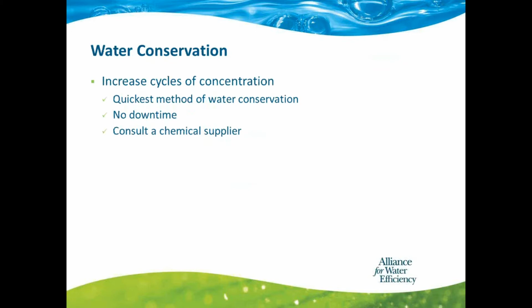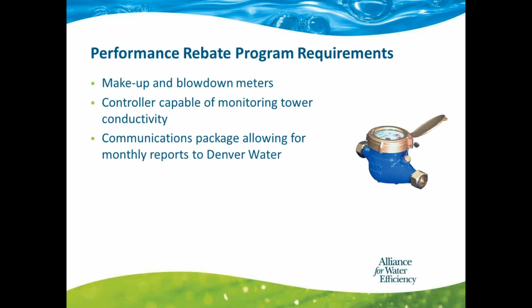The easiest way to save water in cooling towers, of course, is to increase the cycles of concentration. This is the quickest method we've seen for water conservation. There's no downtime, but you want to be sure to consult your chemical supplier, making sure that whatever path you choose does not harm the tower or the environment. That is your first decision.